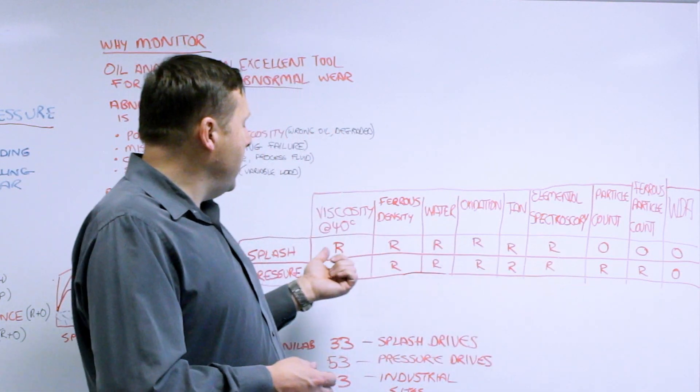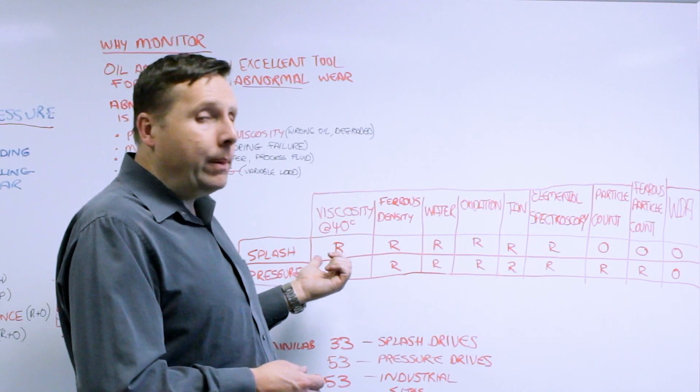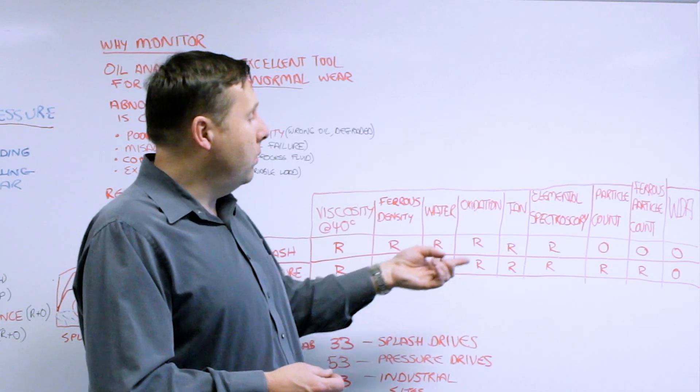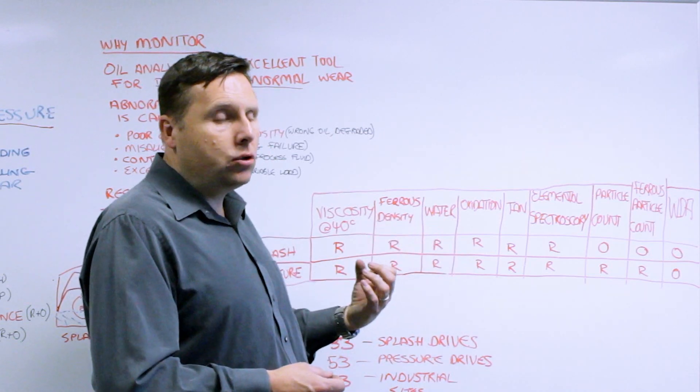Particle count, we say it's optional for splash lubrication systems. They're usually high viscosity above an ISO 320 so ferrous density is a great screening tool.